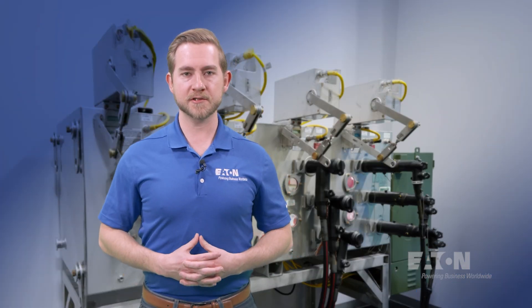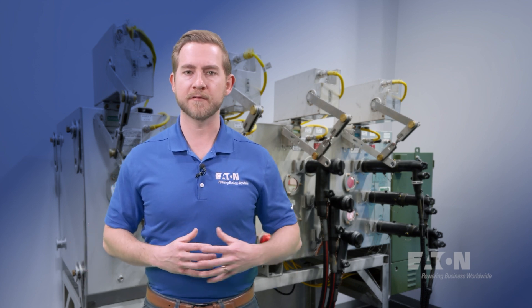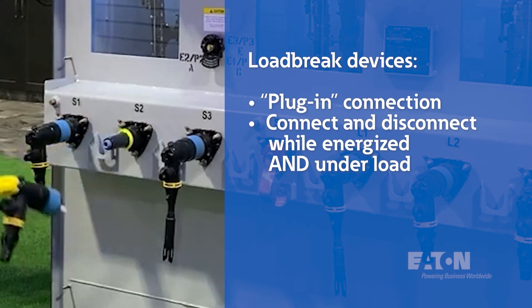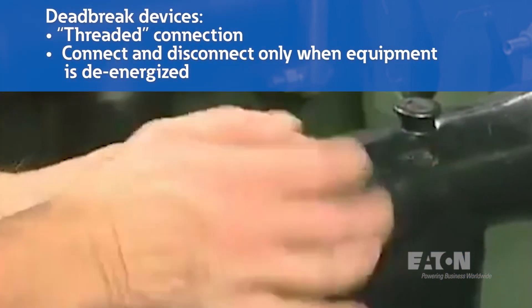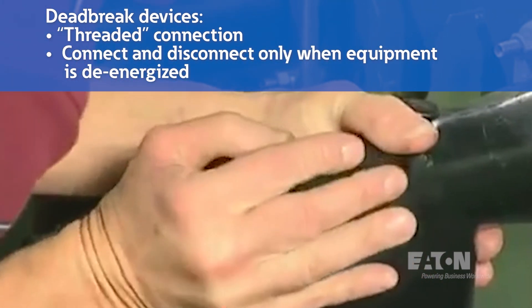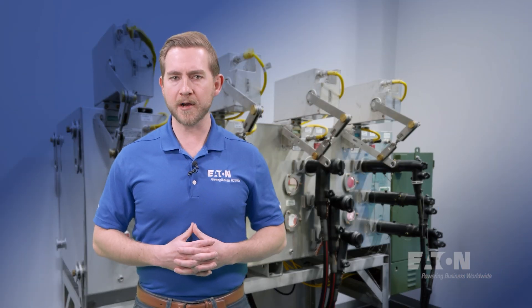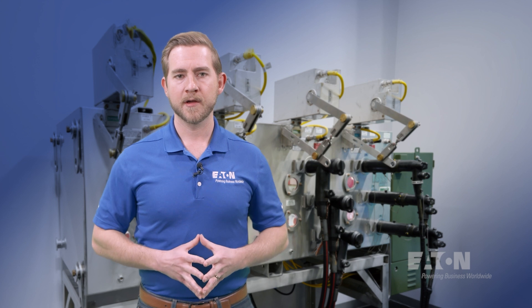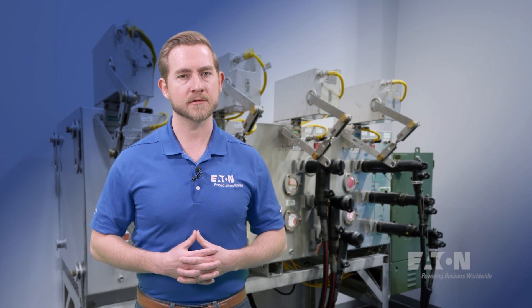Similar to the terminology just discussed, it's important we understand the difference between load break and dead break devices. Loadbreak devices allow an operator to make or break a connection while the equipment is energized and under load. Conversely, if a piece of equipment or application is deemed dead break, the equipment must first be de-energized for any operation on that equipment. Often, dead break applications require the operator to interface with exposed and possibly live parts. This is why it is crucial the equipment be de-energized in any dead break application, unless noted otherwise.